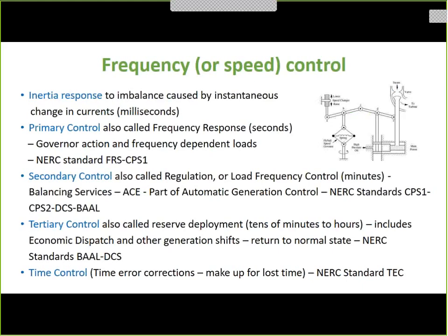There are what I would call five or six steps here. The first one is inertia response. You know, when you turn on a light, you're going to cause something to slow down. It has to. And when that happens, the governor will react and open up the steam valve and get more steam in, which brings the speed back up. So when you turn on a light, you're slowing down a generator. The governor will detect that because of the change in frequency, and it will increase the steam valve to make it go faster. That's the primary control, the governor.